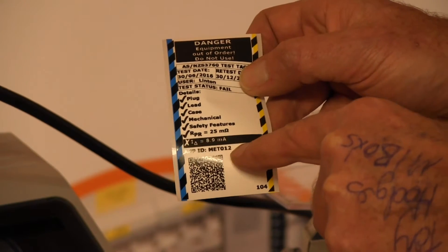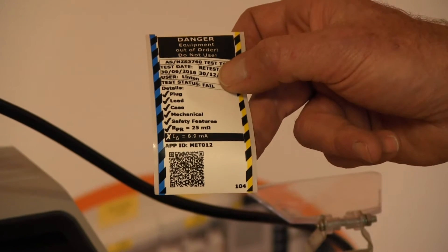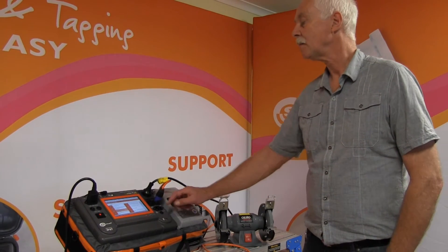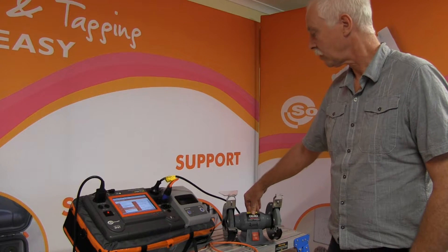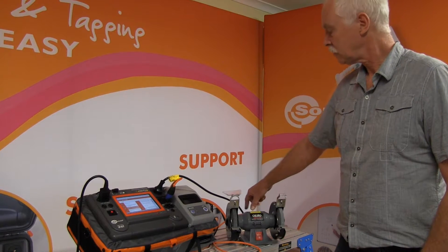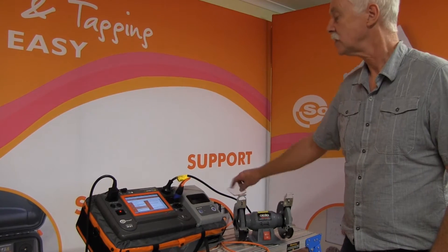The fault shown is the leakage being 8.9 milliamps. We'll now go ahead and do the test but without doing the leakage test — this time we will do an insulation test. We're now back to do an insulation test on this class 1 appliance. As the previous test showed, it failed the leakage test, so we're going to see what happens when we do an insulation test.